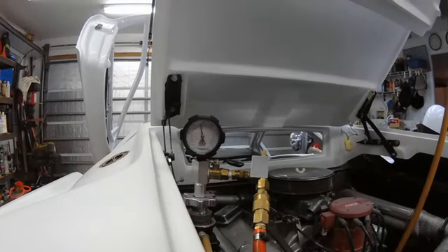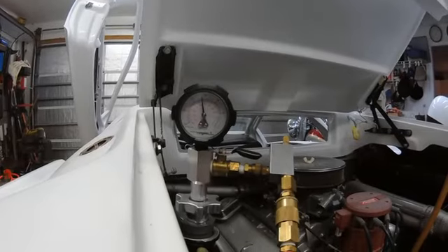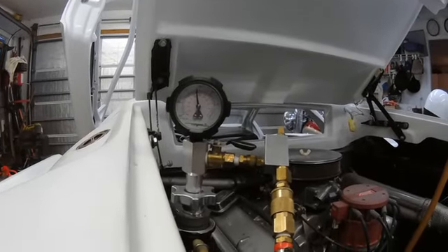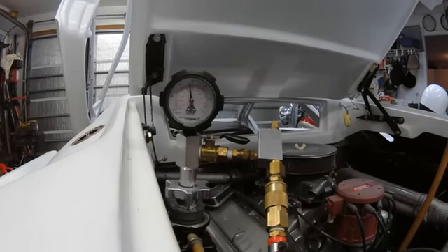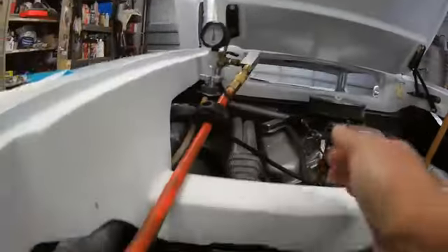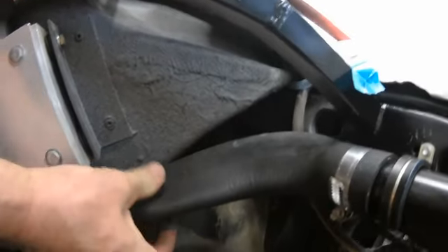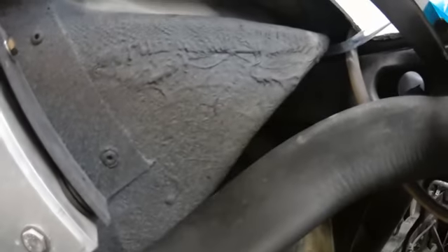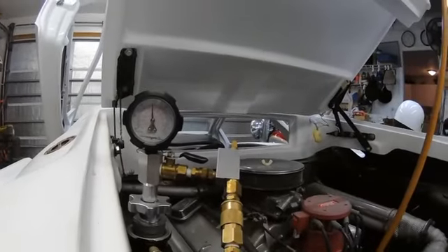Well it's been almost an hour and it's still vacuuming down. I've got about 16 inches of vacuum right now and I need 23 inches. So it's still climbing - and you can really tell it's pulling a vacuum big time now because this hose is completely smashed, totally together. Luckily that's the only hose, but it's kind of nice to know that it's really pulling hard. I guess it's just going to take a while - hopefully another half an hour and it should be at 23.